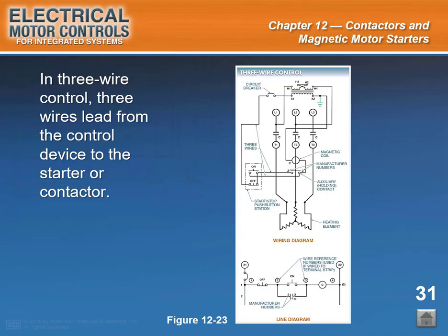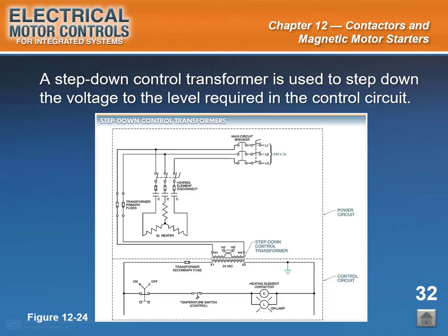Start of slide 32. Slide caption: a step-down control transformer is used to step down the voltage to the level required in the control circuit. See Figure 12-24.